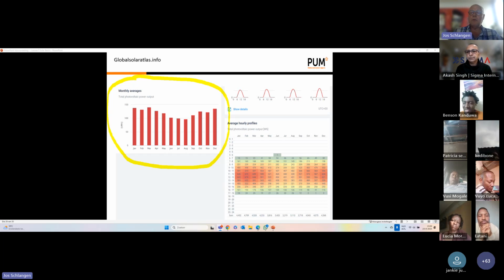When you want to add more solar panels to existing ones to increase power generation, is it doable, or do you need to replace all the panels? Will the new panels overpower the old ones, or merge to give the desired power? I'd need more information on the situation, but the general advice is to connect the new panels to a separate inverter, or at least a separate input of the inverter. Do not connect them in the same string as existing panels, but always connect them in parallel to other strings. When you have space and want to increase the system, that's very much doable, but always keep in mind you have to secure your overpower ratings, fuses, or whatever you have in the system, so you don't blow out the whole situation for the customer.